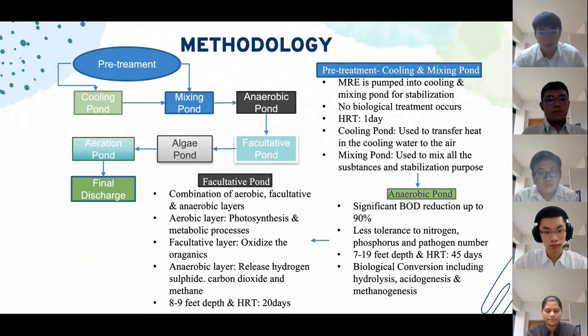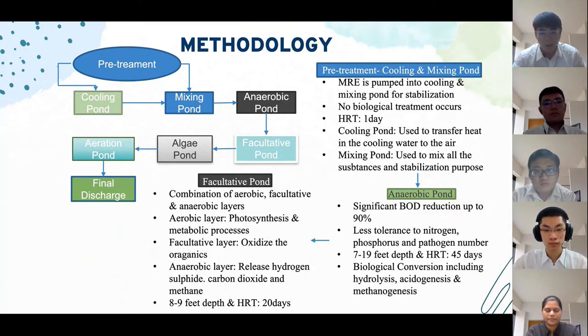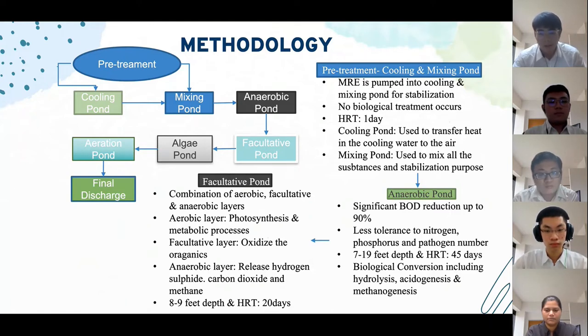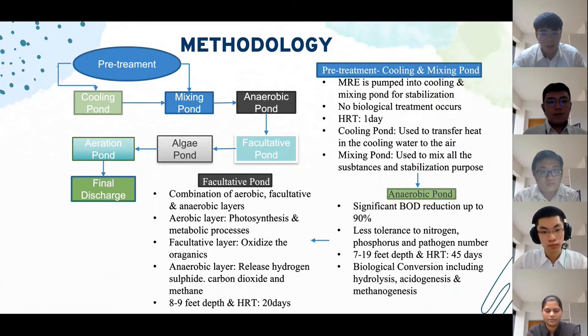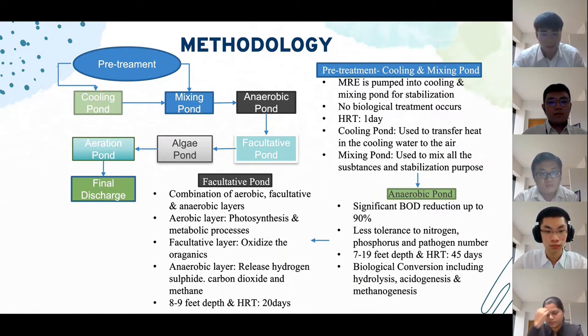Moving to primary treatment, the first pond is the anaerobic pond. Anaerobic digestion is one of the most useful biological treatments, giving very significant BOD reduction of up to 90%. However, it has less tolerance to nitrogen, phosphorus, and pathogen numbers. Anaerobic ponds are usually 7 to 19 feet deep to minimise the presence of oxygen and maximise heat retention. HRT for the anaerobic pond is 45 days. There are three steps of biological conversion of organic matter: hydrolysis, acidogenesis, and methanogenesis.